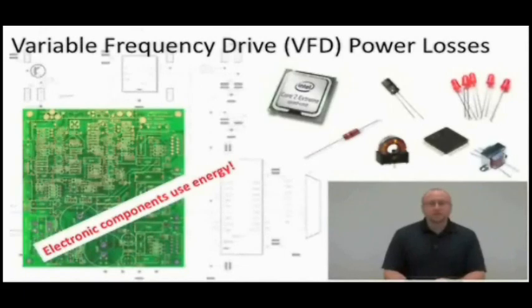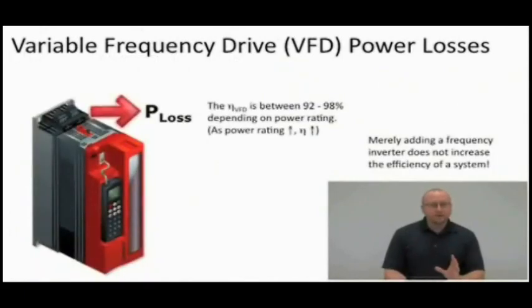So there are losses inside of a variable frequency drive. But usually, variable frequency drives are very efficient, relatively speaking: 92 to 98%. The efficiency of a variable frequency drive actually depends on its power rating. Because we have those losses in the control section, basically the computer part of the inverter, as the inverter gets larger and larger, the losses in the output section are a bigger portion. So the control section losses are almost minuscule or insignificant compared to the overall losses, and the inverter has a higher efficiency rating. The efficiency is actually a unitless rating, like we mentioned earlier.